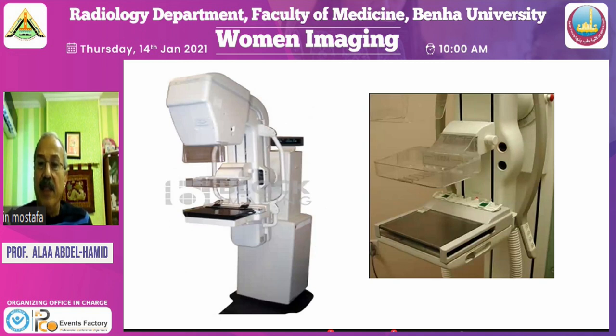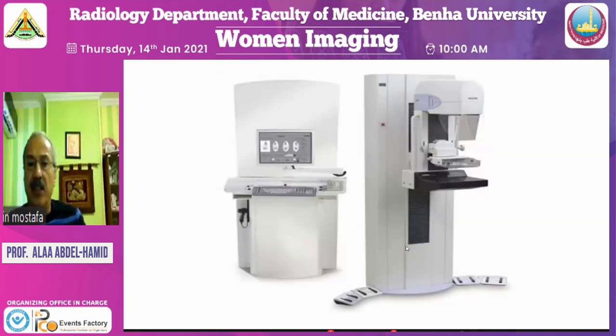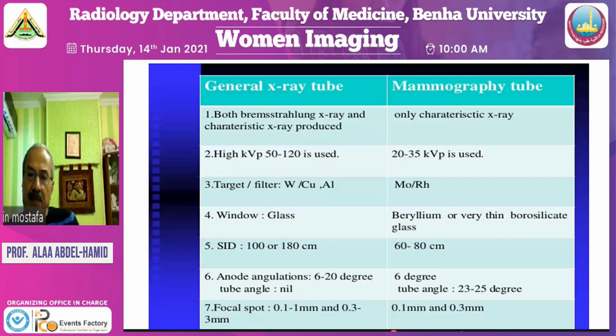This is the analog mammographic machine. The image here shows that the machine is composed of a tube housing here, the compression paddle, and the film housing. We will introduce the film here through this opening, and the grid is present in front of it. We have a photo timer behind the X-ray film in order to control the parameters of examination. This is the digital machine. As we see here, it's the same as the analog machine, but the electronic detector is present here. And this part of the machine is changeable. We can change it to different sizes.